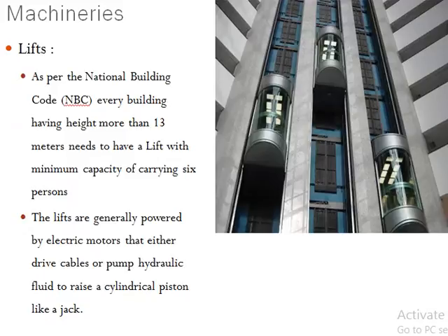As per the National Building Code, every building having height more than 13 meters needs to have a lift with a minimum carrying capacity of 6 persons. So that is the National Building Code. Then, lifts are generally powered by electric motors that either drive cables or pump hydraulic fluid to raise a cylindrical piston like a jack.